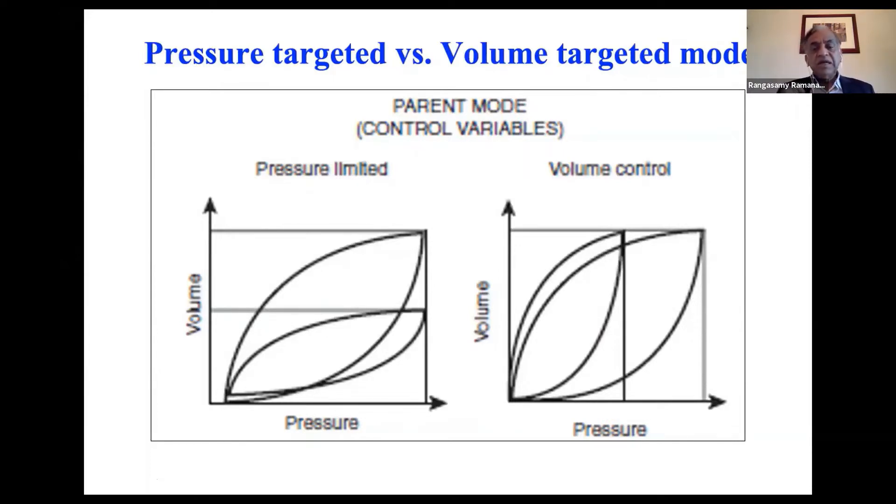Volume guarantee mode needs a flow sensor, especially at the Y, and adds expense, adds some dead space. That is why a lot of centers, even in the US, are still using pressure control mode as the most common one.